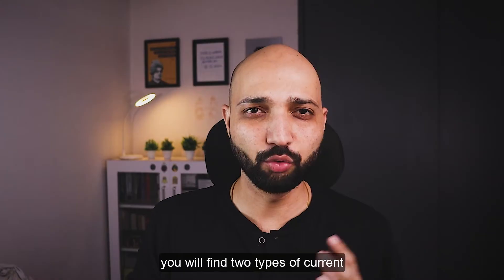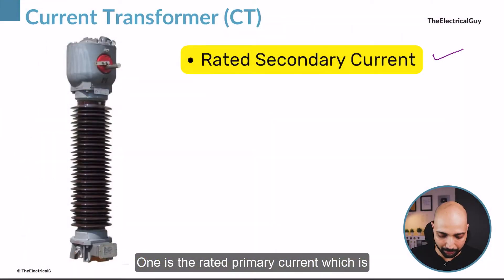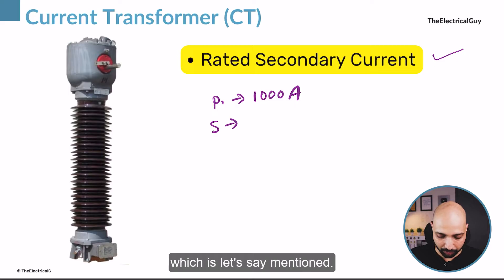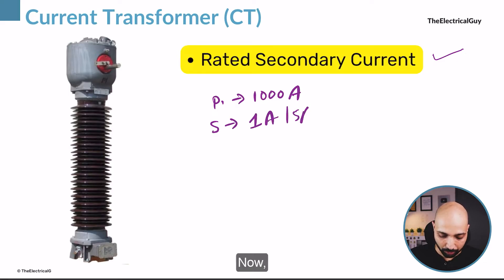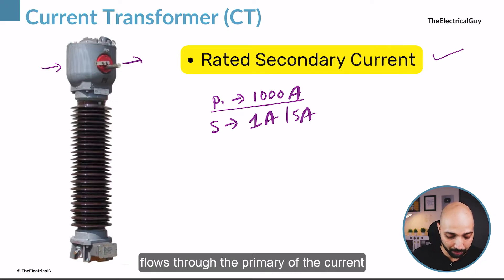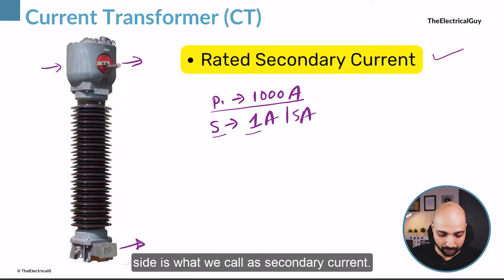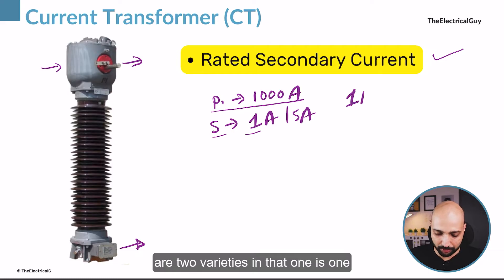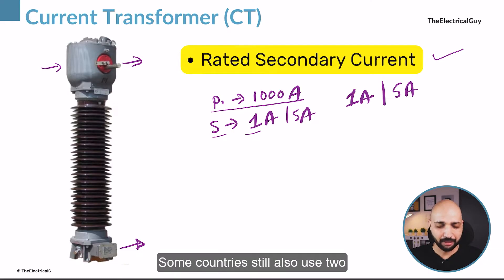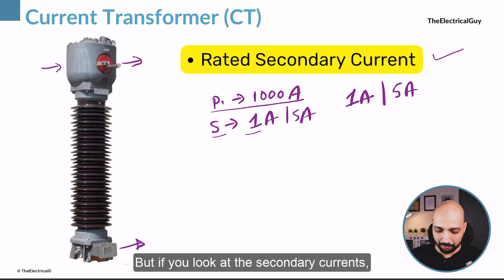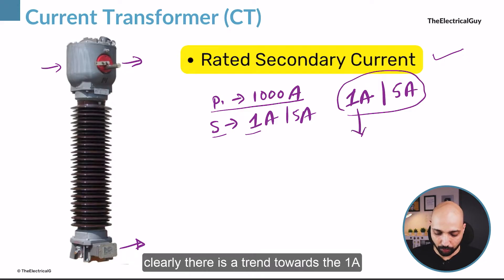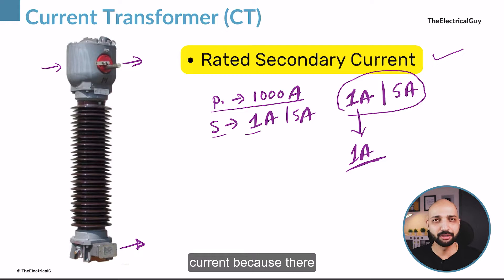Let us start with the rated secondary current. If you look at a current transformer, you will find two types of current mentioned on the nameplate: one is the rated primary current, let's say 1000 ampere, and also a secondary current, mentioned as 1 ampere or 5 ampere. The primary current flows through the primary of the CT, and the output from the secondary side is the secondary current. The secondary current generally comes in two varieties: 1 ampere and 5 ampere.